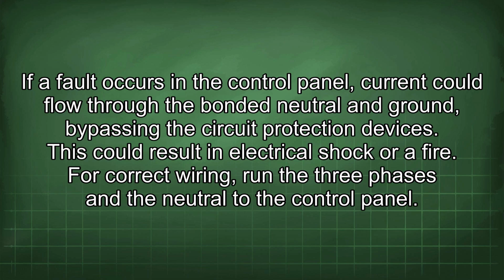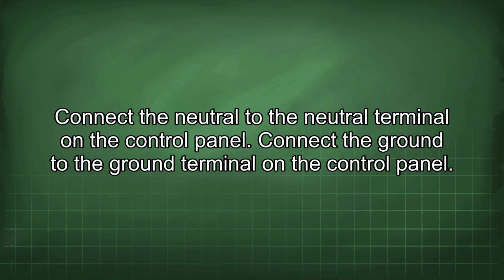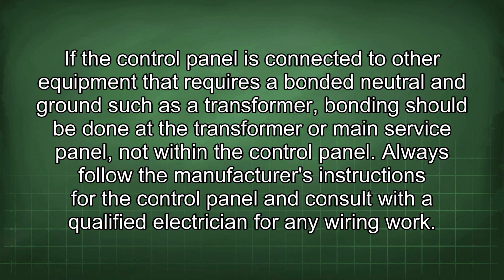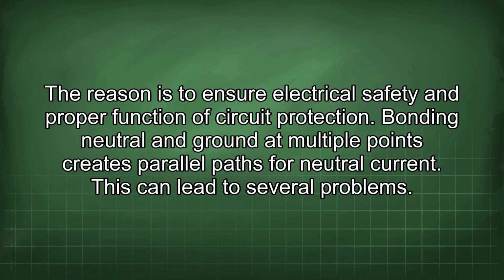For correct wiring, run the 3 phases and the neutral to the control panel. Connect the neutral to the neutral terminal on the control panel. Connect the ground to the ground terminal on the control panel. If the control panel is connected to other equipment that requires a bonded neutral and ground, such as a transformer, bonding should be done at the transformer or main service panel, not within the control panel. Always follow the manufacturer's instructions for the control panel and consult with a qualified electrician for any wiring work. The reason is to ensure electrical safety and proper function of circuit protection.